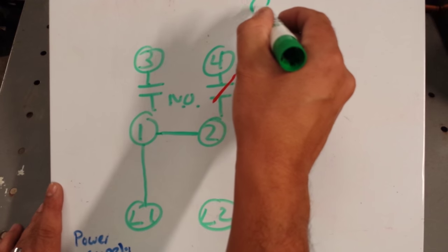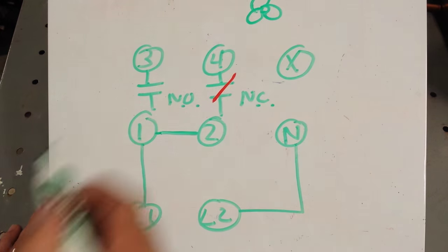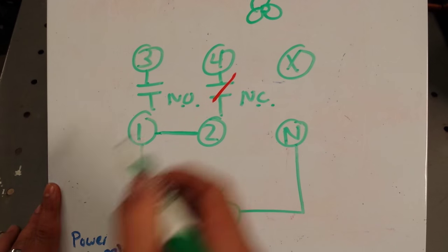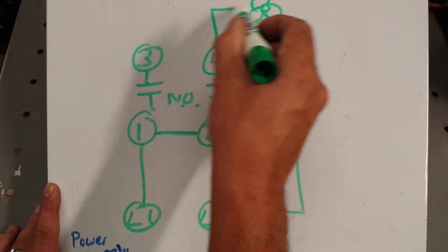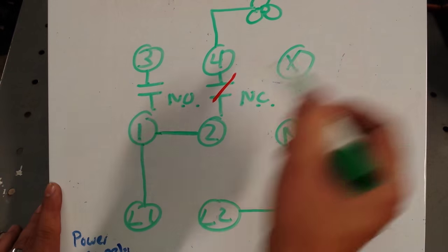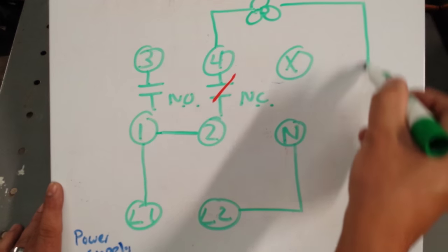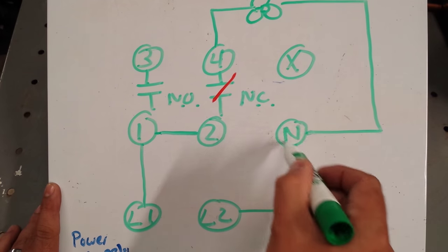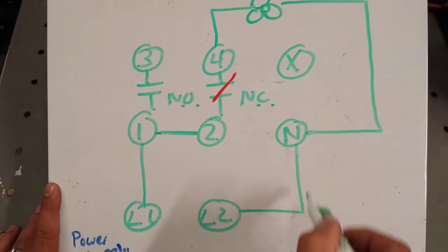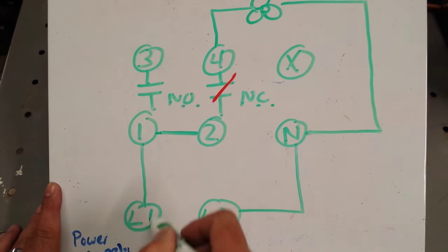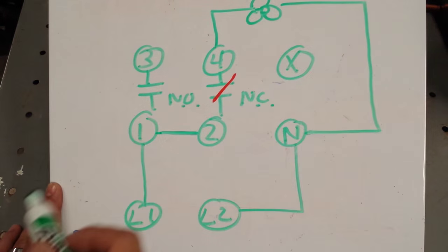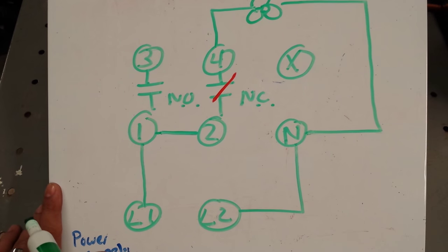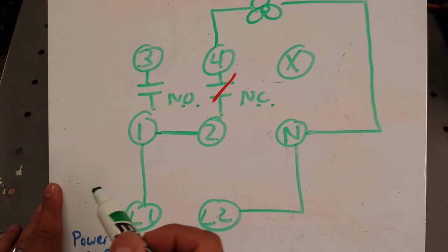So we'll just draw a fan motor picture here to represent our evaporator fan. And we'll put 4 to it there. And if we complete that circuit bringing that fan motor back to L2, L2's in on our defrost clock, that completes the circuit. Which means this fan should be running.